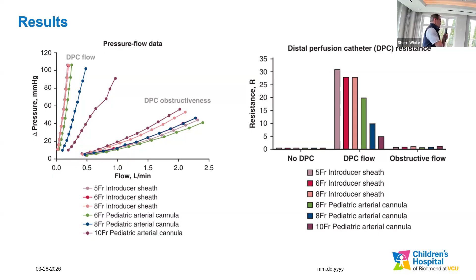So looking at the dynamic flow loop results, and this is where it gets interesting, is when you actually put it into the working model of cardiac failure. The 3 pediatric arterial cannulas provided an increase in the cumulative flow to the distal right superficial femoral artery. The 3 introducer sheaths provided equal or actually less cumulative flow to the right superficial femoral artery. And the cumulative flow was calculated as the right superficial artery obstructed flow plus the distal perfusion cannula net flow.